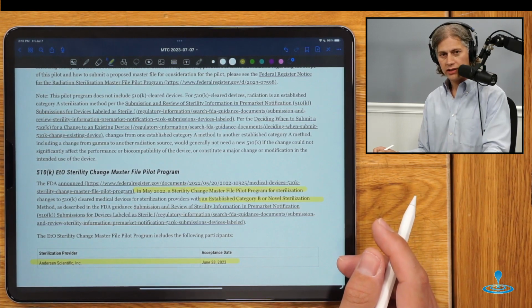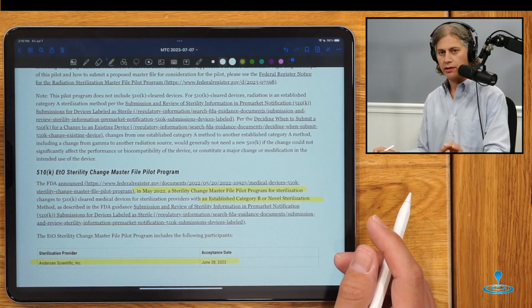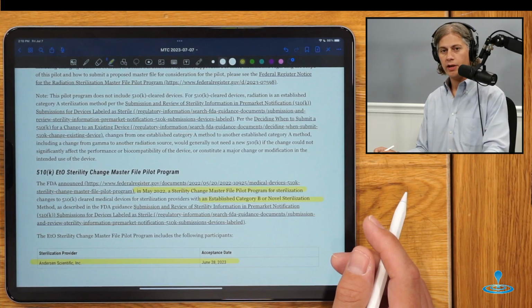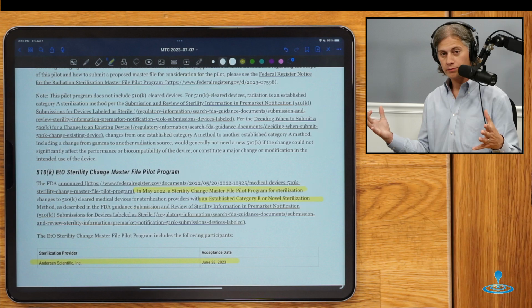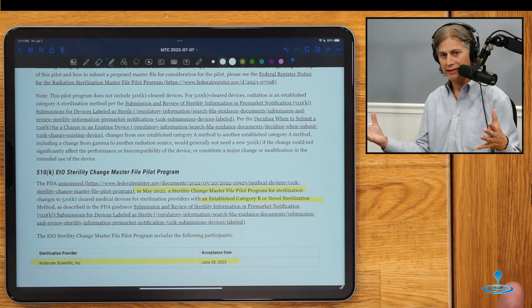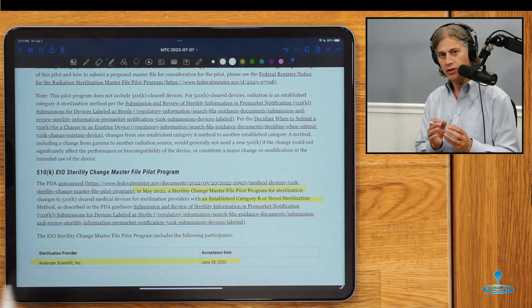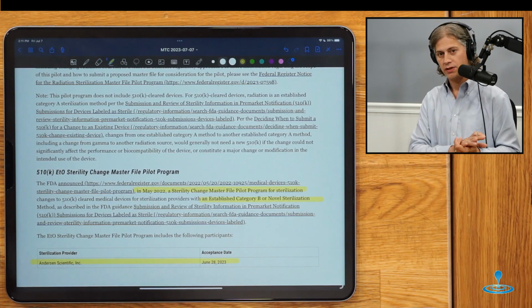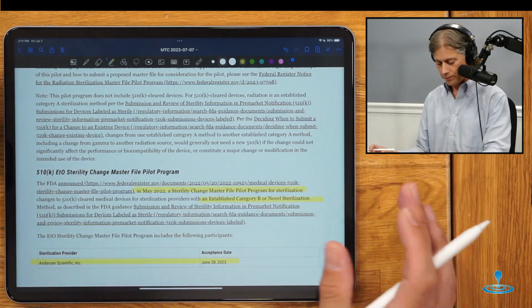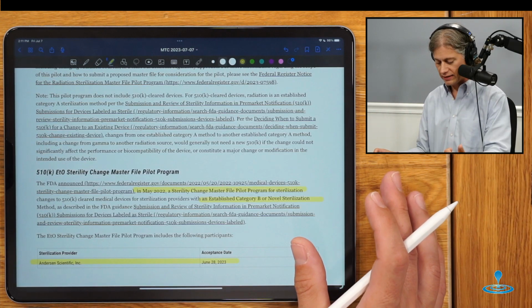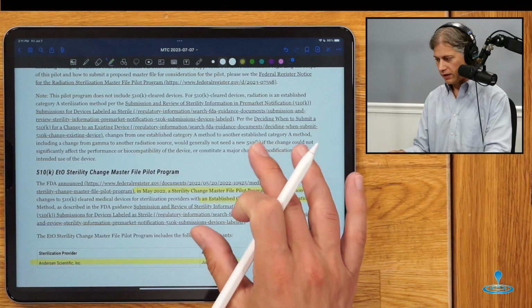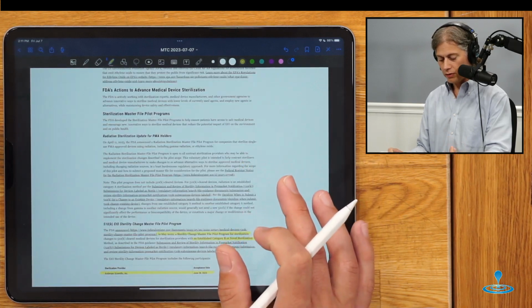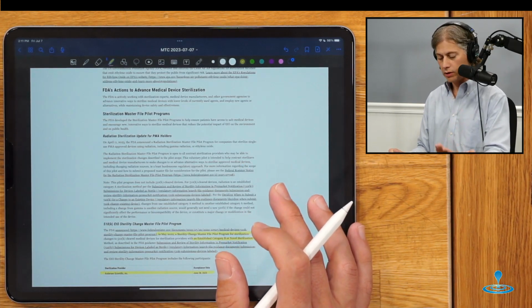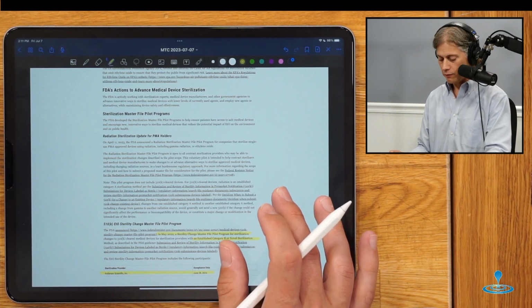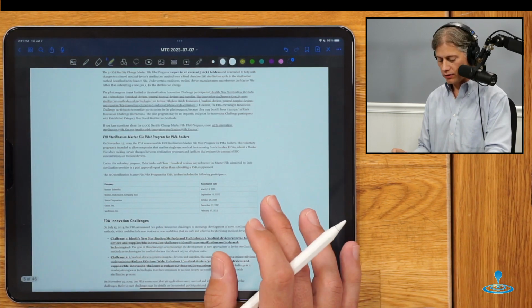And it actually makes a lot of sense if you think about it. It's still using ethylene oxide, but the way they're reducing the amount is they have a flexible chamber. And the flexible chamber can fill up with ethylene oxide, but it can then be collapsed down so the EtO can be retrieved instead of just vented into the atmosphere. So Anderson has this. They've got a master file with FDA. That means some relatively good news that people who are using their method now will hopefully not have to resubmit for a 510K if they need to change sterilization methods.